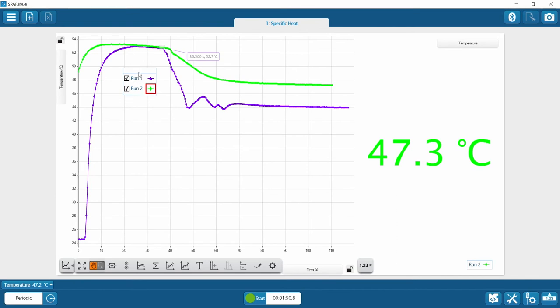If you need to do any more analysis on either Run 1 or Run 2, make sure in your SPARKvue legend that the red box is around the run you want to analyze. Click to put the red box on Run 1 or Run 2 accordingly. The digits display shows the last recorded data point — the final temperature. Toggle between runs by clicking the run name to switch. Now we have enough information to continue with the analysis.